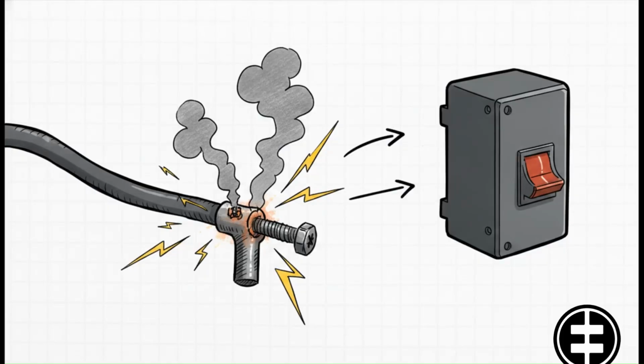Now, you might think the big, expensive circuit breakers are the most vulnerable parts of the whole system, right? Actually, experience shows us the real danger lies somewhere else entirely. The main components are usually totally fine. The true risk is the wiring itself. Bad connectors, poorly executed bolted joints, or improperly placed metal supports can silently destroy those carefully planned insulation values. That's exactly why connections in bundles of conductors are so meticulously checked during these type tests.